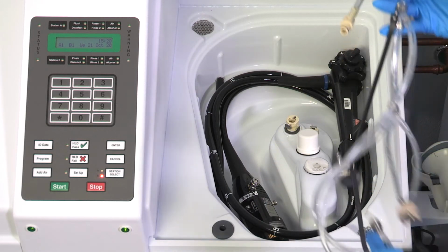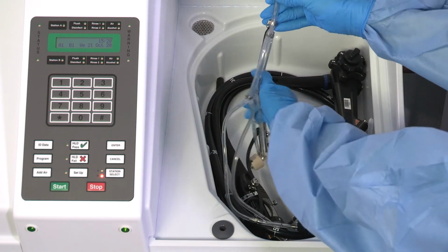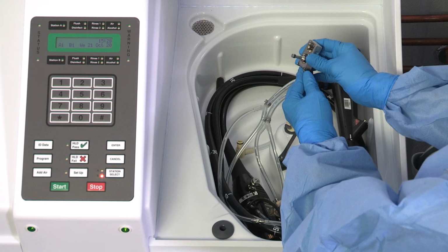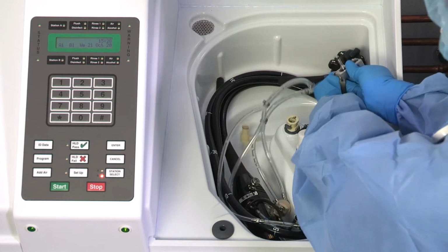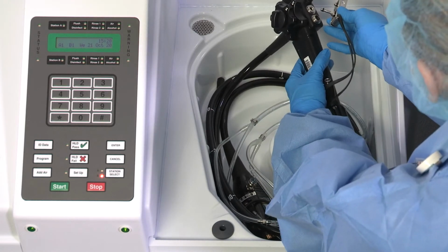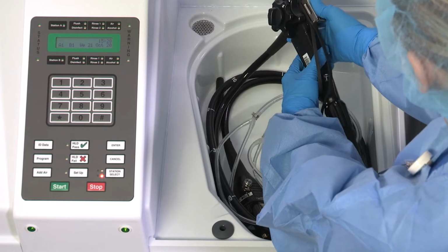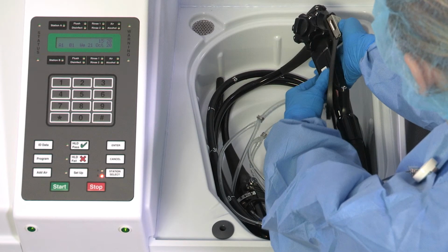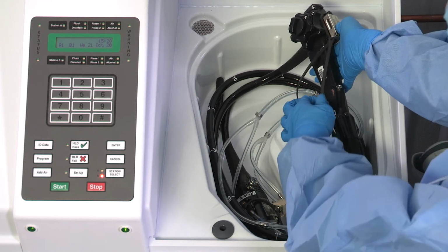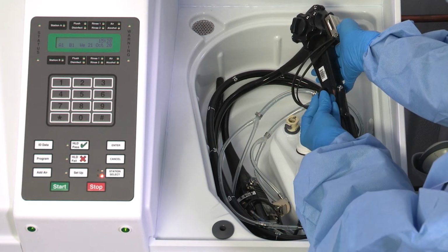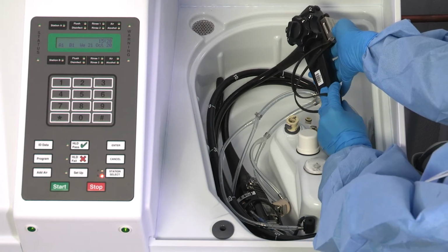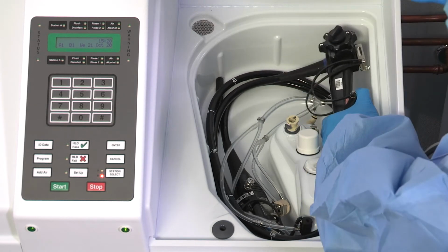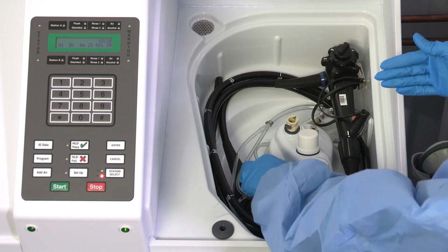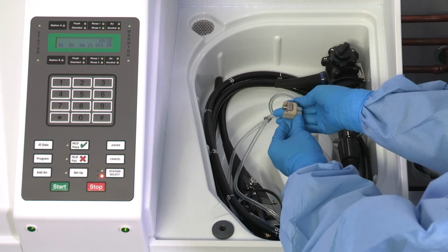Next, connect the hookup to the endoscope. Let's start with the air-water and suction separator. Ensure the release button is pushed in. Place and align the separator over the valve cylinders or openings. Push down on the channel separator until the release button moves out and you hear an audible click. For the biopsy inlet connector, align the rubber fitting over the instrument channel port and push down and over the inlet until fully engaged. Next, we will attach the air-water connector.